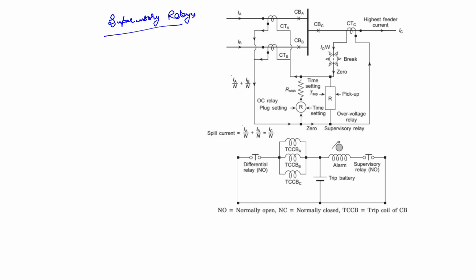At other times there may be a break in the pilot wire coming from the particular CT secondary winding. Thus, even though there may be no internal fault in the busbar, an imbalance is created because of that on the secondary side, causing a spill current which is equal to the current that was being contributed by a particular CT before its secondary got open circuited.